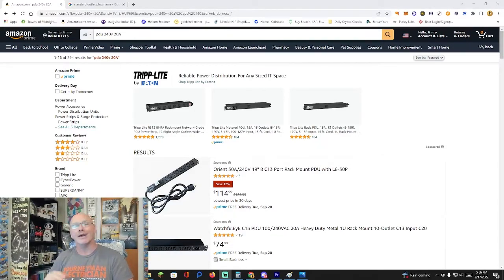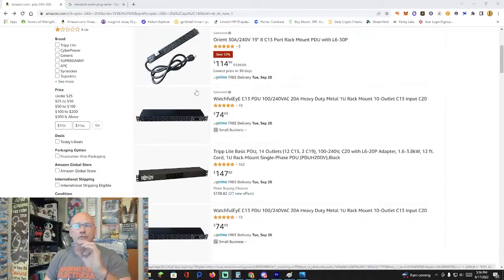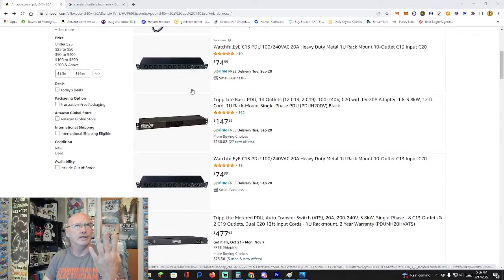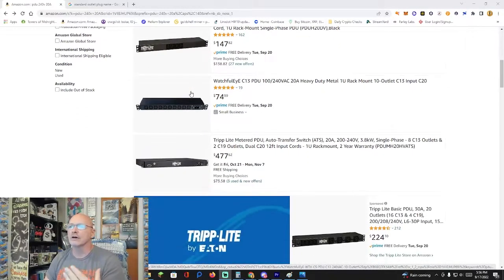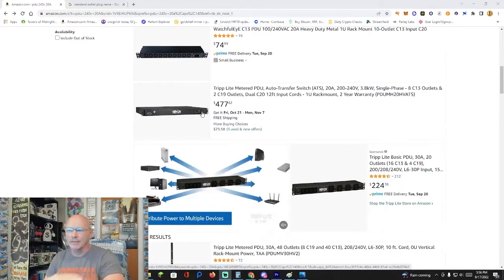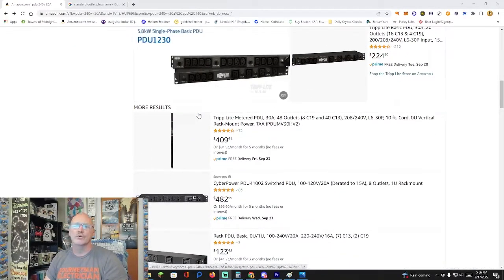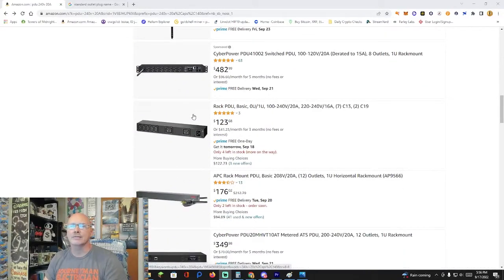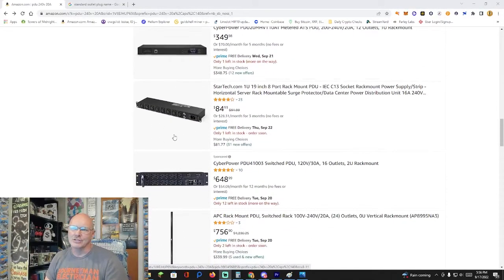So the next part is what kind of PDU do I want? So we're going to jump over here to Amazon, and I did a search of PDU 240 volt for a 20 amp circuit because that's what I decided to design for this. And I'm looking for the C13, C14 connections. I know I need at least 5 per PDU unit because that's how many devices we're going to plug in. And there's a lot of variations. Then we start looking at it has a metering system or monitoring or surge arrestor or inline breaker system. A lot of different things, as well as a C19 connector like this guy right here, which I don't need because just with the 5 machines I've got, that's going to fill up all the outlets. So I just need 5, and I'm not seeing just 5.